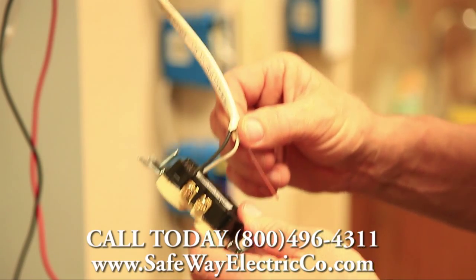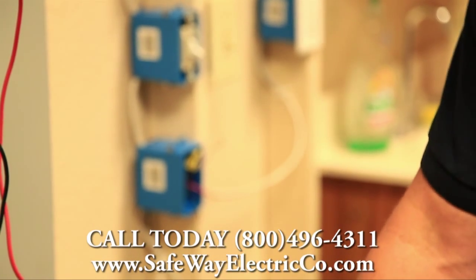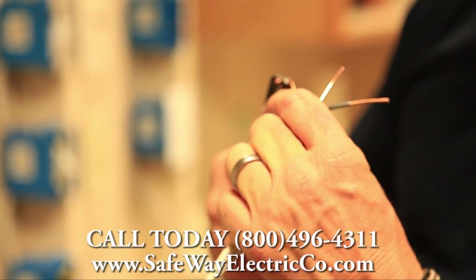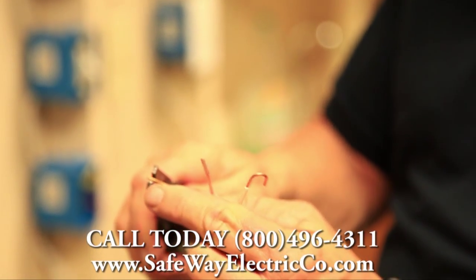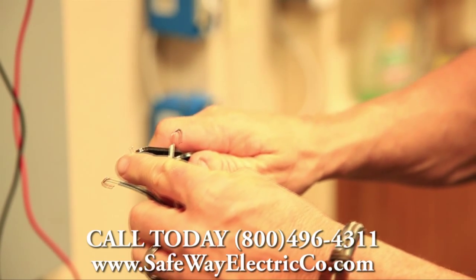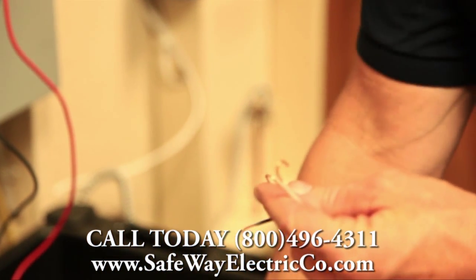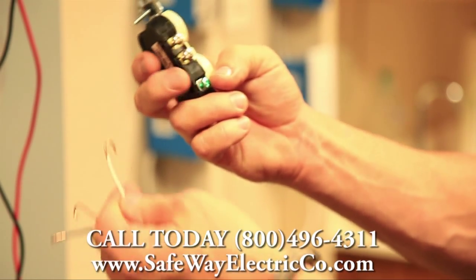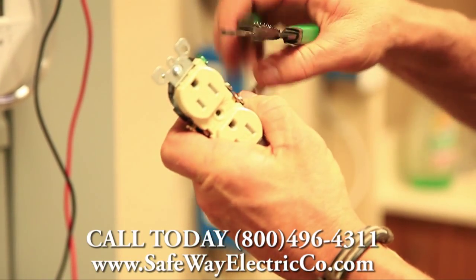That heat usually burns up the wiring, burns up the receptacle, and sometimes even causes a fire. So this is not the preferred method. What we like to do here at Safe Way Electric is strip off the insulation just enough to get a nice loop — on the white wire, the black wire, and also the ground wire. The loop always goes in the direction that you're going to tighten the screw.